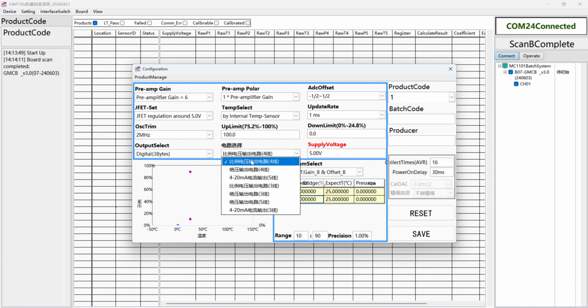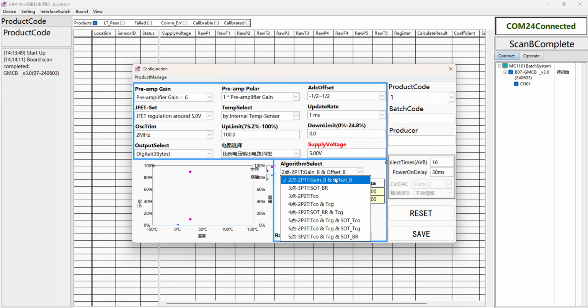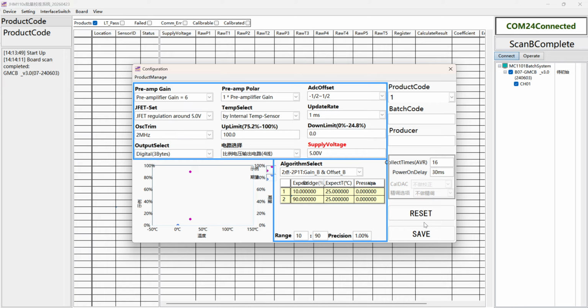And here is the original voltage output, absolutely voltage output, 4 wires. Here I choose the original voltage output, 4 wires, and here we can see this is the digital output. So here is 10%, and here is 90%. I will select this algorithm, 2 point in 1 temperature. So now I will save it. This is the difference between the digital output, the analog output for voltage, or something else. So I will save it.